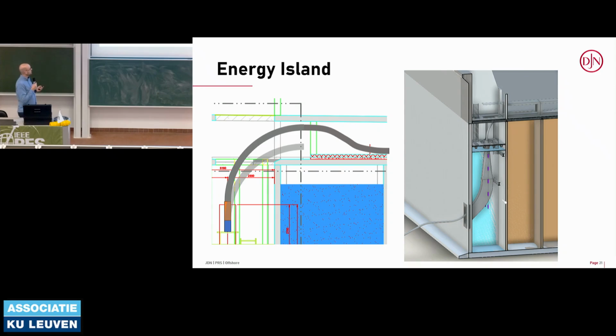Not only that, because we're pulling in a cable over here, but as Thierry already mentioned, a joint is very complex and is usually the point of failure. If you have a failure in your cable, 95% of the time it's the joint. So what we do is foresee a room for retermination, meaning we have to pull an extra cable to make sure we can terminate it, and re-terminate it if needed to do it once more.